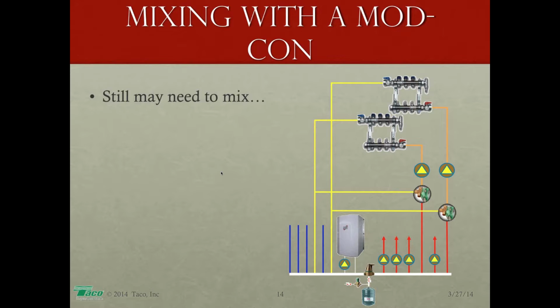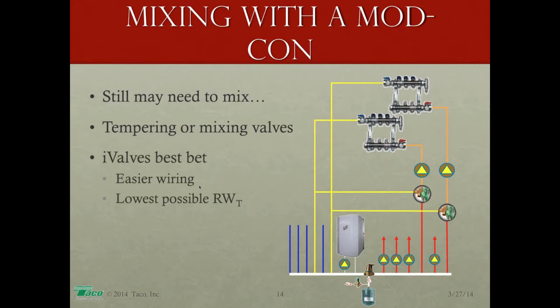And then our basement slab maybe needs 110 degrees under design conditions. We can set up a second mixing station there. Now, the benefit of doing this, especially if you use something like the iValve, you use a tempering valve or a mixing valve, but a Taco iValve is a motorized mixing valve, and you have outdoor reset built into those little green heads on each one of those.